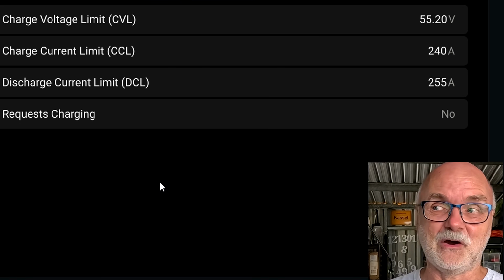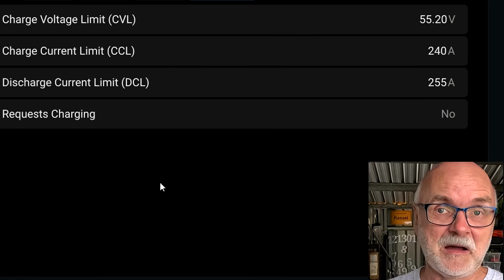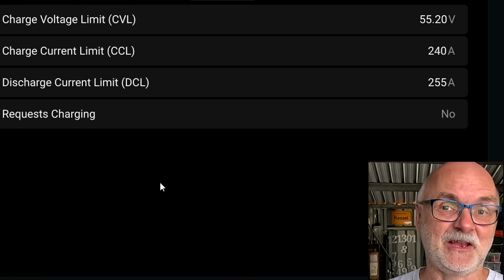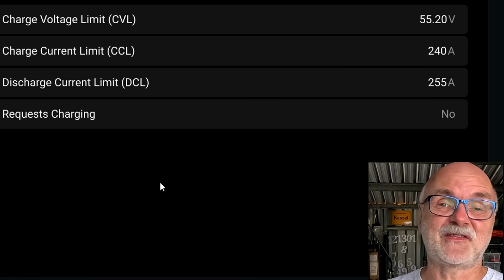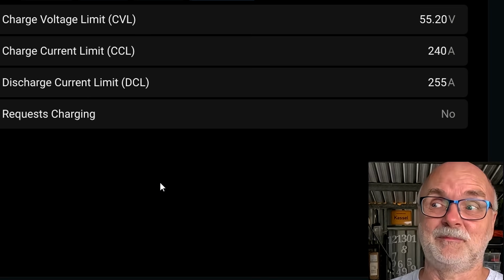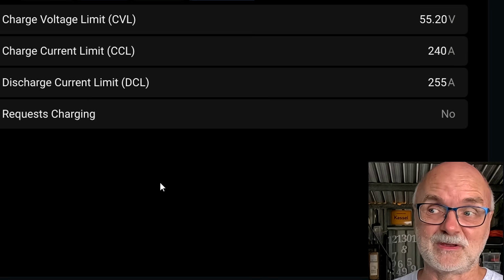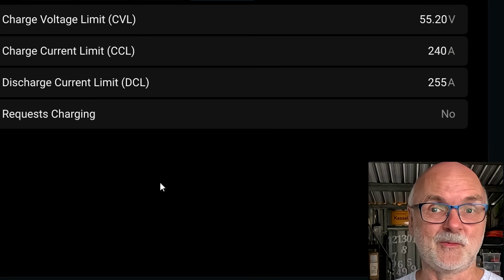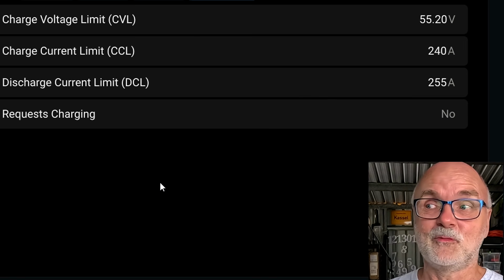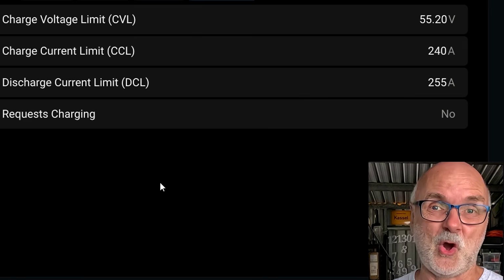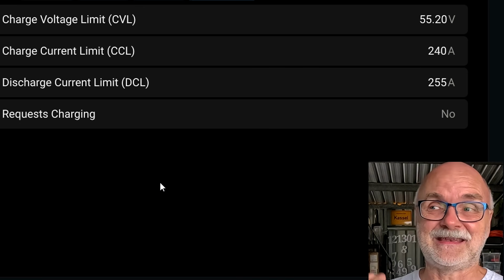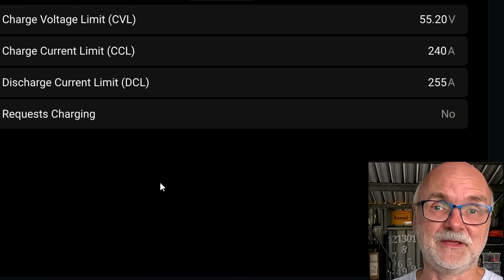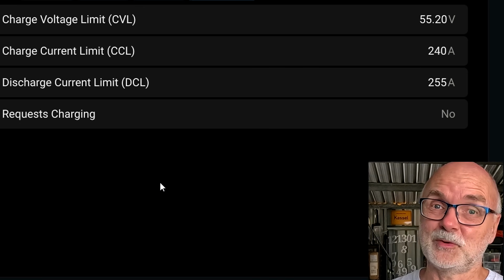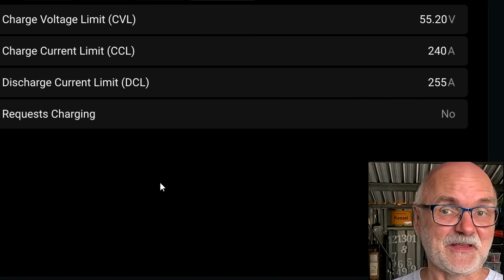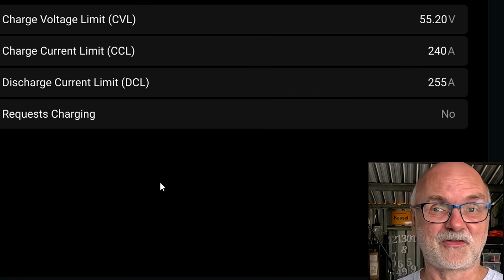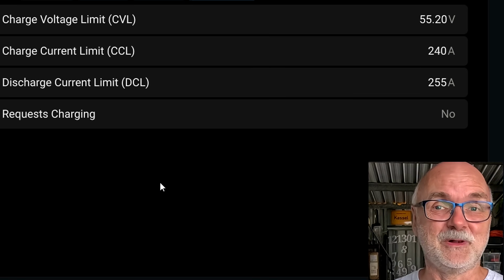And now we get a cell over voltage condition, and the BMS is not catching it, because the master BMS thinks we have only 3 batteries connected, since it can communicate with these 3 BMSs, but not with the 4th one anymore. But exactly in this battery, we have a problem with one of the cells. We've got an overcurrent, we've got an over temperature, and nothing would be reported to the master BMS anymore. So this could potentially lead to a little disaster. You are overcharging your battery over 3.65 volts and nobody will know about it.